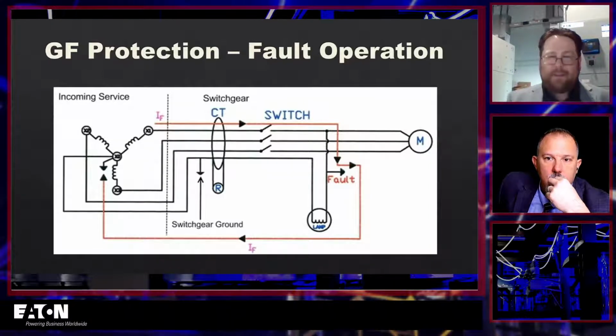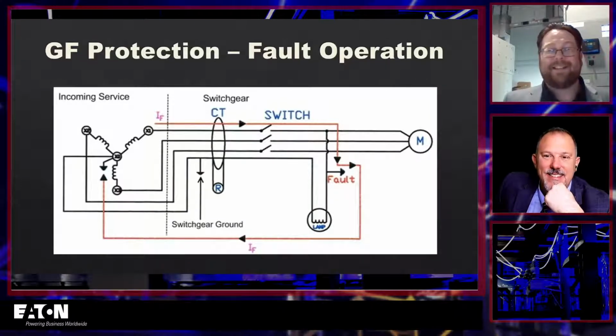It took some time, but after a lot of investigation over months, we figured out that every single time their ground fault tripped, they needed to change a lighting ballast in the gymnasium, because one of the ballasts would fail. It would resistively short to ground and cause just enough current that, over time, it would increase until it reached the level where it would trip. But lights in a gymnasium are 30 or 40 feet up in the air. You don't go change a light bulb on that. You wait till like six or seven of them are out, and they didn't know they had this issue.